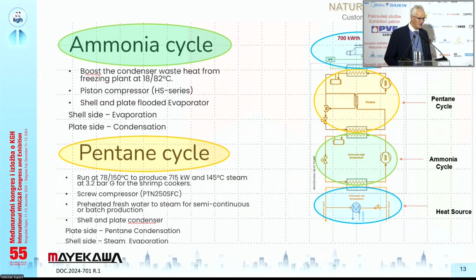By using the heat pump combination, which is in fact a cascade heat pump, because we have the ammonia heat pump, which is kept on the lower temperature, 82 degrees, because of the ammonia and pressure limitation. And we put on a second stage heat pump with pentane, which takes the heat source from the first, or I call it medium temperature heat pump, and pumps it up to 150 degrees.